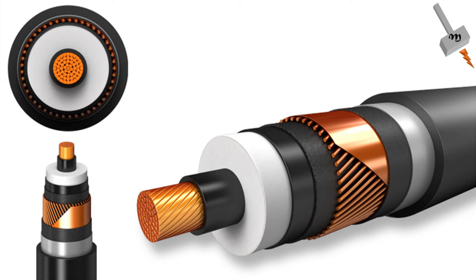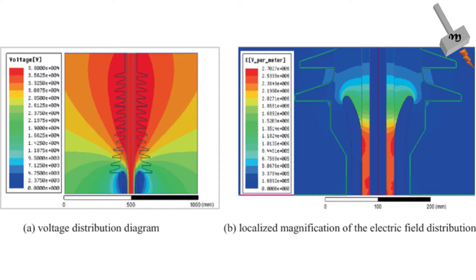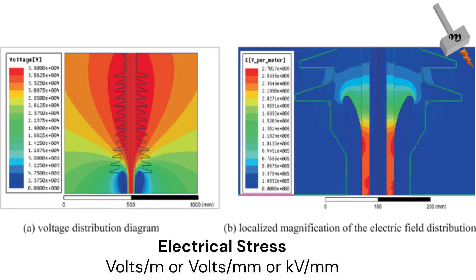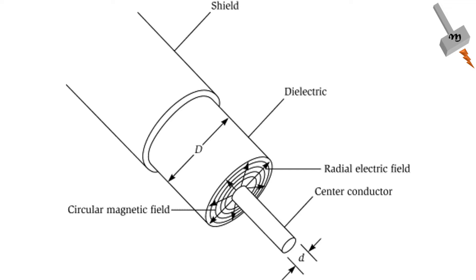High-voltage cables are engineered to minimize electrical stress on insulation. Electrical stress is measured in volts per meter. Cable shields are provided to achieve symmetrical and uniform electrical field distribution around the center conductor, thereby minimizing electrical field stress.